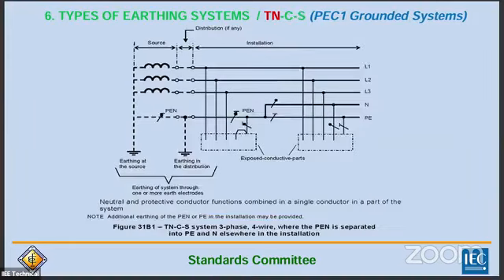Okay, then we have the TNCS, which is one factor na kung makikita niyo, doon sa una, TNC, di ba? TNC siya. Yung PEN kasi may PEN ginamit niya at the same time, so 3-phase, meron siyang PE, protective at neutral din dadaan doon. Pero nung pinaghiwalay niya doon sa distribution board, yung N, because he needs a line to neutral voltage, so 230 volts for example, then you will run 5-wire na yon. Merong ganitong installation, hindi mo pwedeng baliktarin yan, so you have to follow the rules, yung guidelines na ganyan pag meron kang installation.